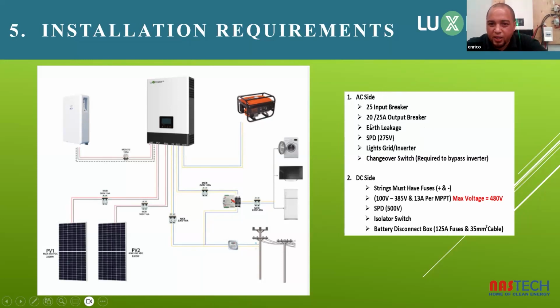On the AC protection side, you also need your earth leakage for any fault current that may occur. A surge protection device of 275 volts. You need your indicator lights for your grid and your indicator lights for your inverter. On the AC side, you also need the changeover switch. This is required to bypass the inverter in case of faults and needing to take the inverter off for inspection and repair.